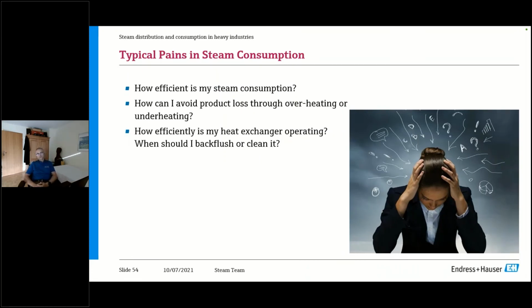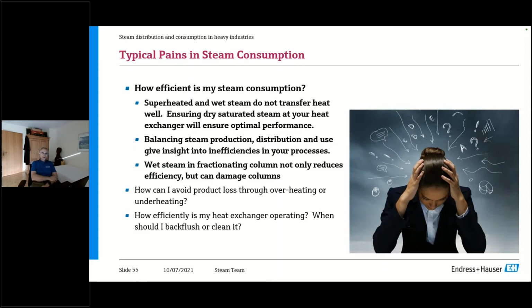So first, how efficient is my steam consumption? We know superheated steam and wet steam, neither is good for transferring heat. Too much superheat, we keep in mind 25 degrees C of superheat is too much, 15 degrees C is acceptable. And if you have wet steam, that has already lost part of the energy. So we must control the steam supply in such a way that we're as close as possible to the saturation line in most applications. Ensuring dry saturated steam at your heat exchanger will ensure optimum performance.